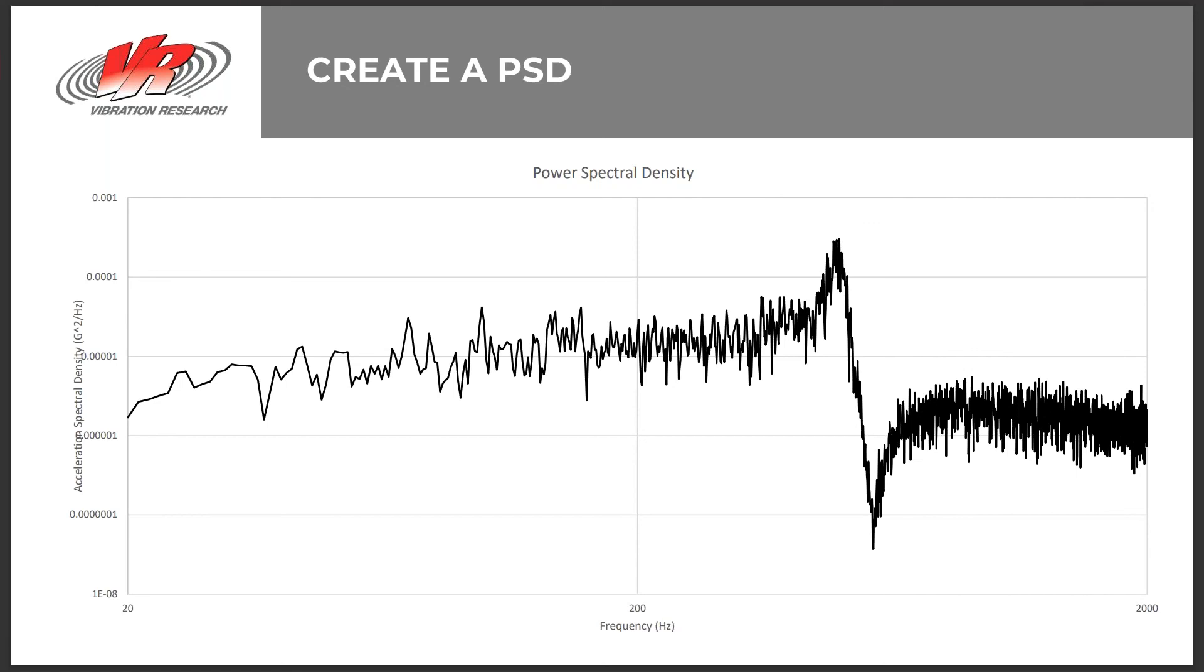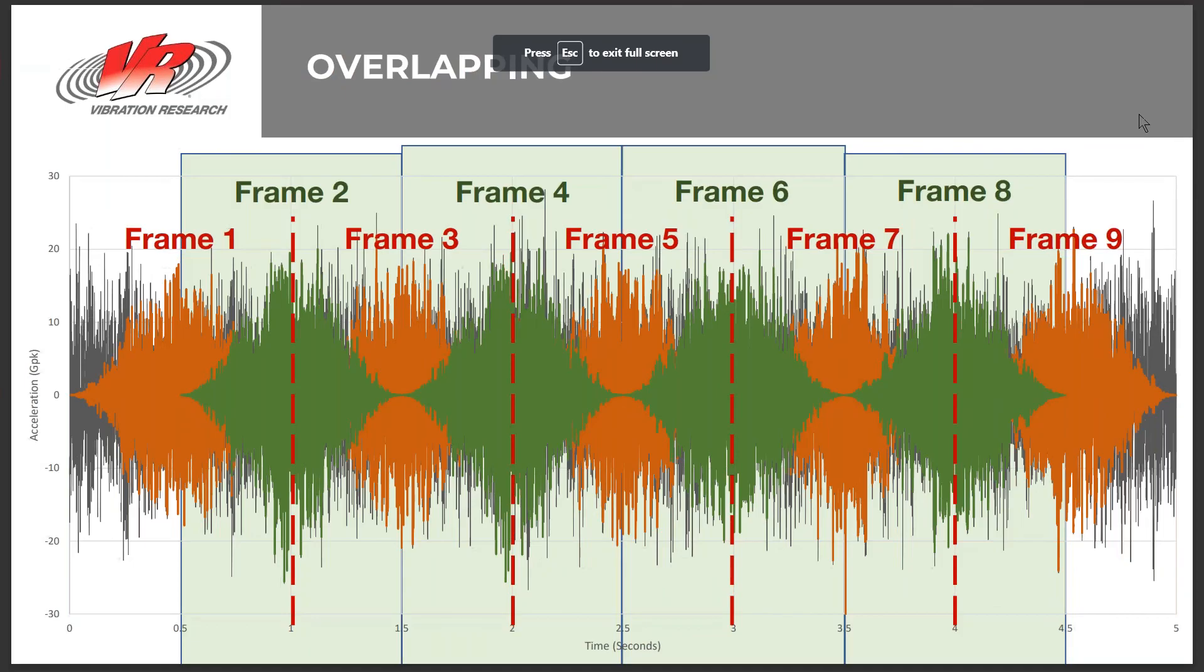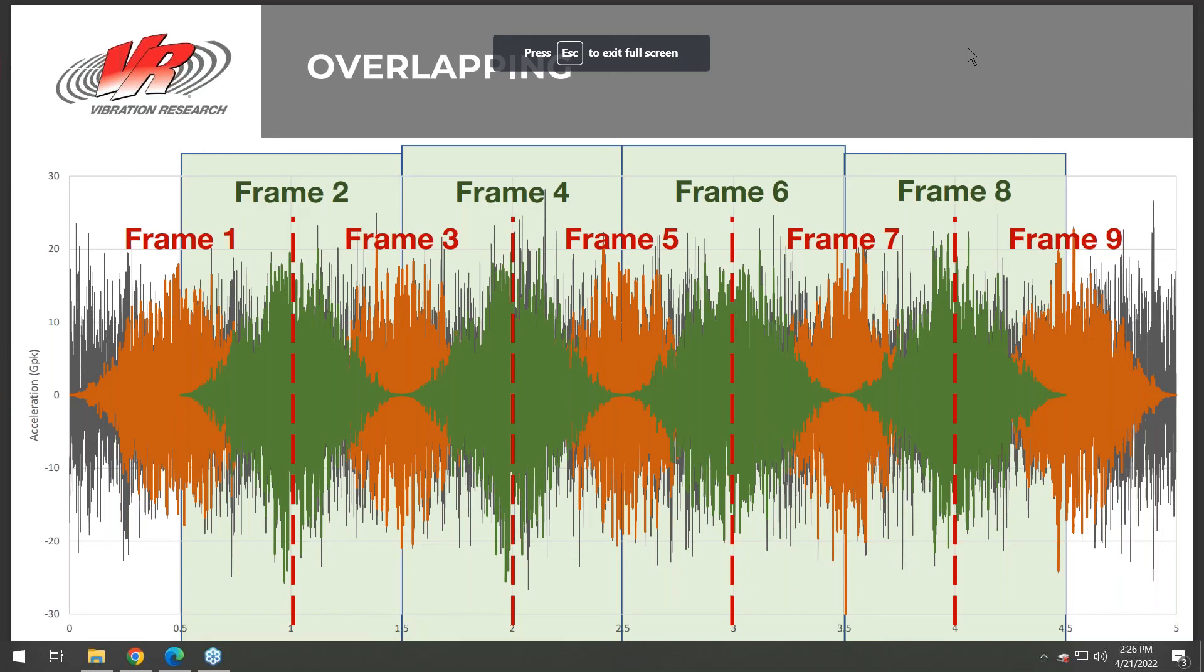The PSD shows the average energy at a single frequency over a period of time. This period of time is determined by an analysis parameter called degrees of freedom. The higher the degrees of freedom, the more frames of data that will be averaged together. More degrees of freedom means more frames of data are being averaged together, which creates a longer period of time to acquire.